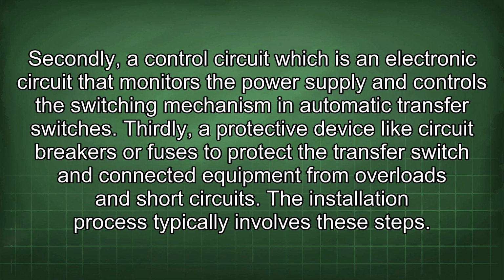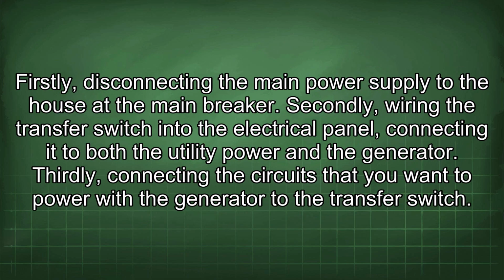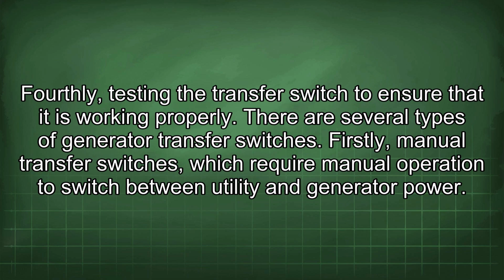The installation process typically involves these steps. Firstly, disconnecting the main power supply to the house at the main breaker. Secondly, wiring the transfer switch into the electrical panel, connecting it to both the utility power and the generator. Thirdly, connecting the circuits that you want to power with the generator to the transfer switch. Fourthly, testing the transfer switch to ensure that it is working properly.